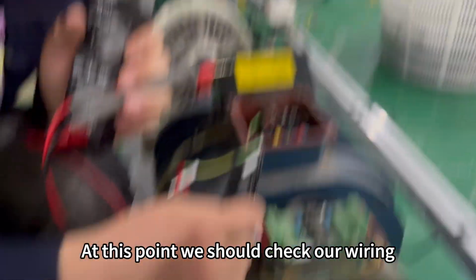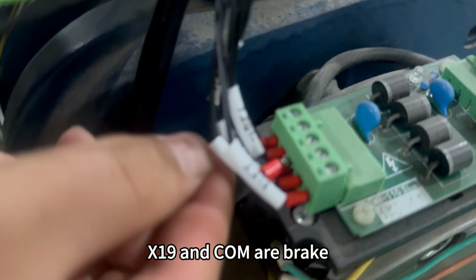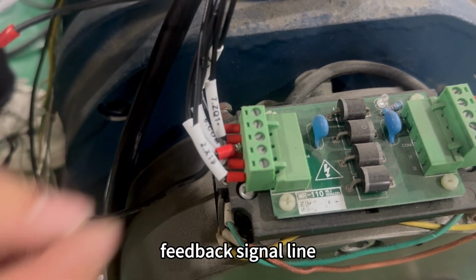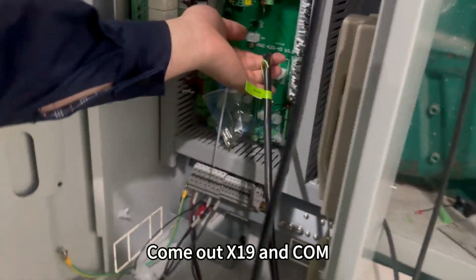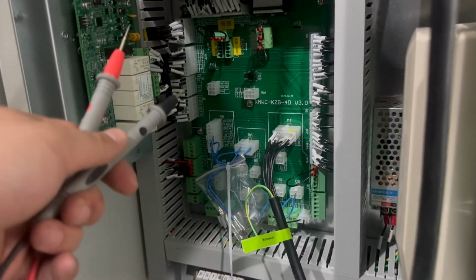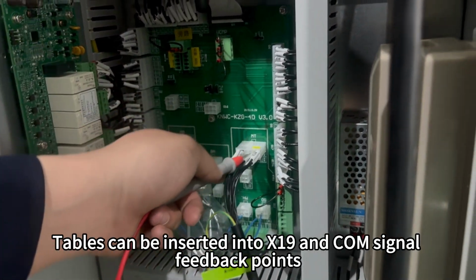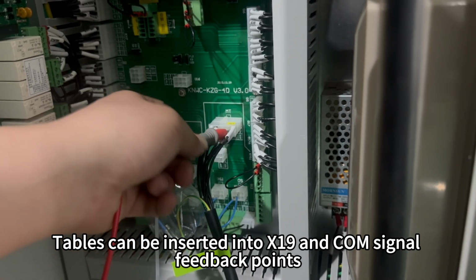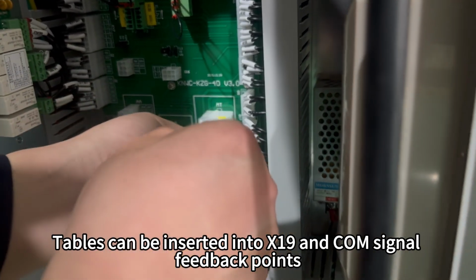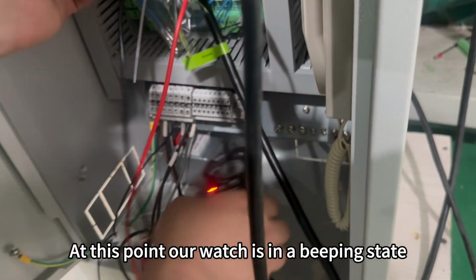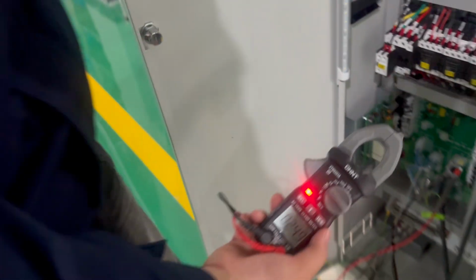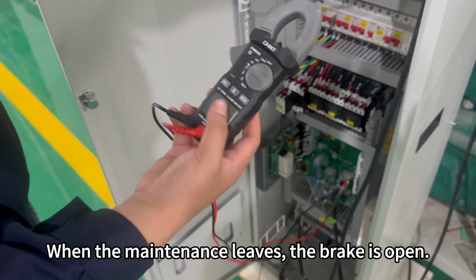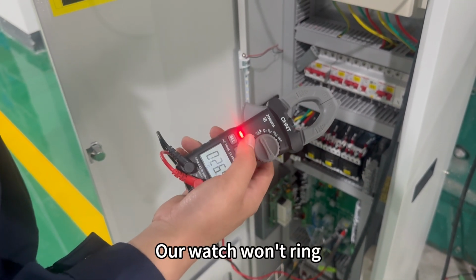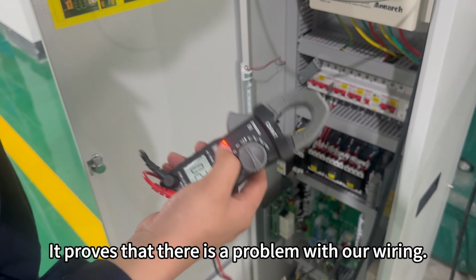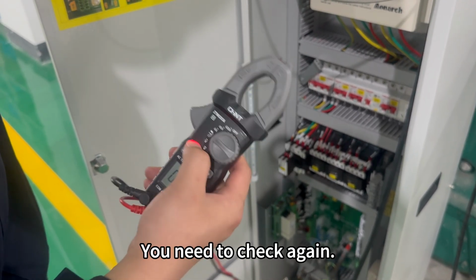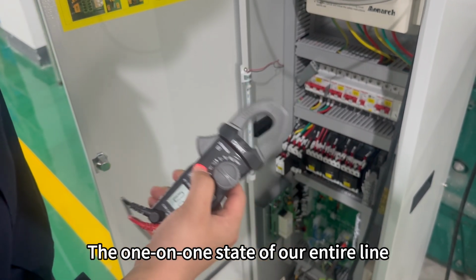At this point, we should check our wiring. X19 and COM, our brake feedback signal line. Here on our meter, put it on X19 and COM. The meter can be inserted into the X19 and COM signal feedback points. At this point, our meter is in a beeping state. When the maintenance button is released, the brake is open. Our meter won't ring, and if it keeps ringing, it proves that there is a problem with our wiring. You need to check again the one-to-one state of our entire line.